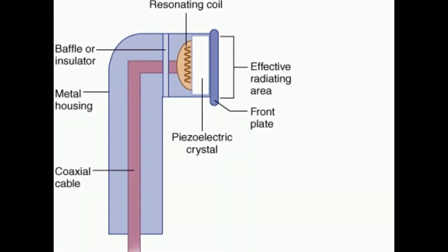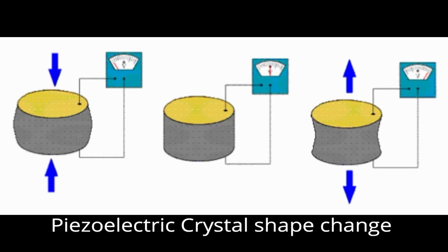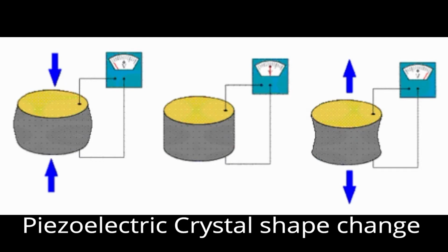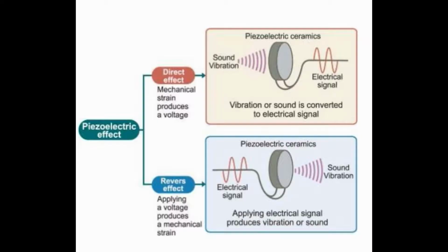In the probe, there are one or more quartz crystals called piezoelectric crystals. When the electric current is applied to these crystals, they change shape rapidly. The rapid shape changes, also known as vibrations, of the crystals produce sound waves that travel outward. When sound or pressure waves hit the crystal, they emit electrical currents. The same crystals can be used to send and receive sound waves. The probe also has sound-absorbing substances to eliminate back reflection from the probe itself, and an acoustic lens to help focus the emitted sound waves.